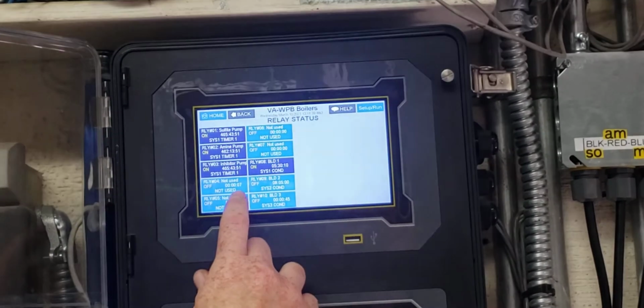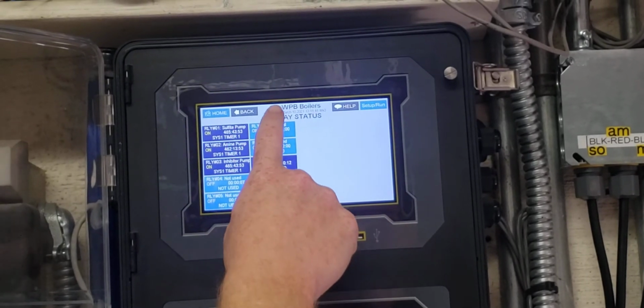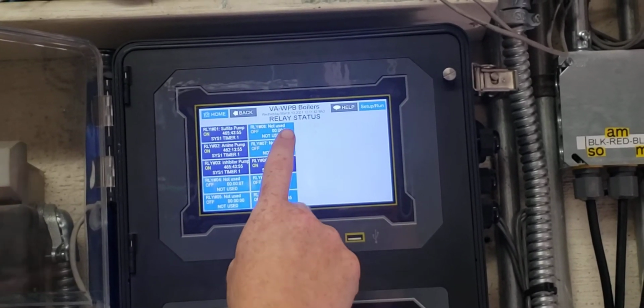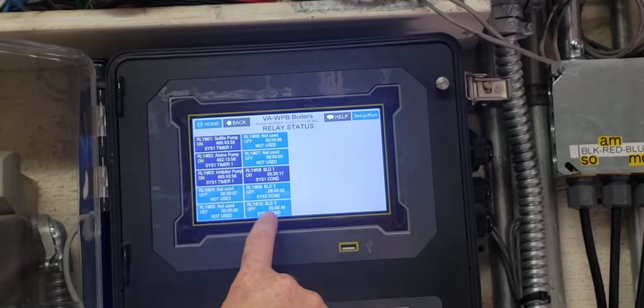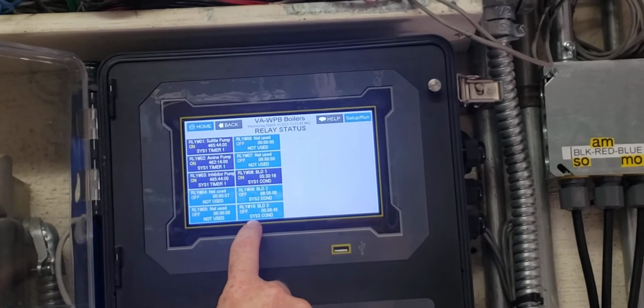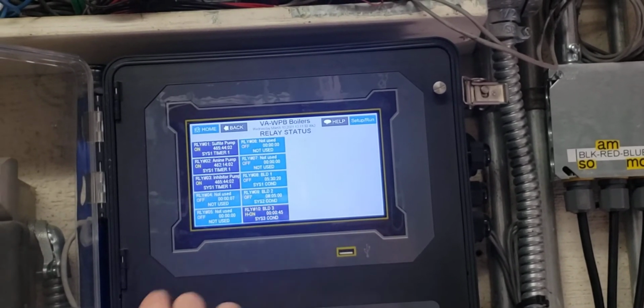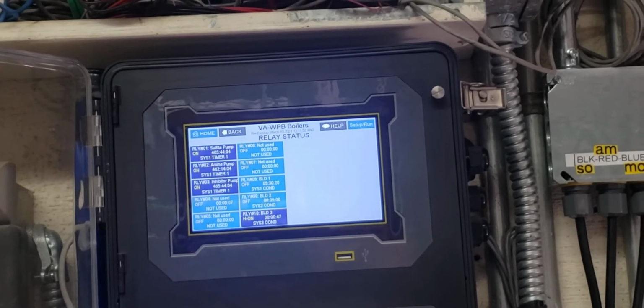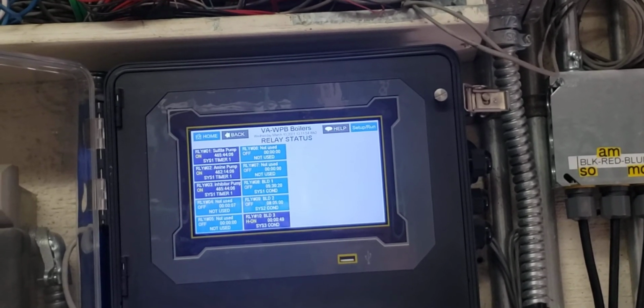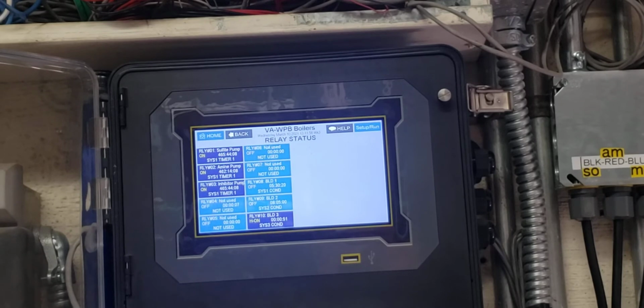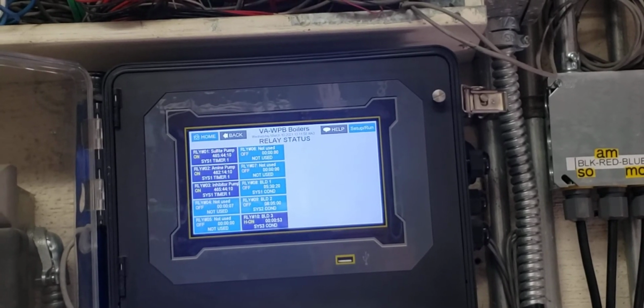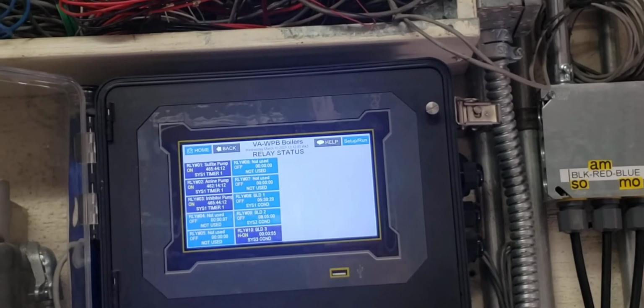So relays, I want to go into boiler 3, so blowdown number 3. I want to go and turn that to hand on. I want it to blow down for a little bit to get a good relative sample on that conductivity probe that's on top of the boiler.